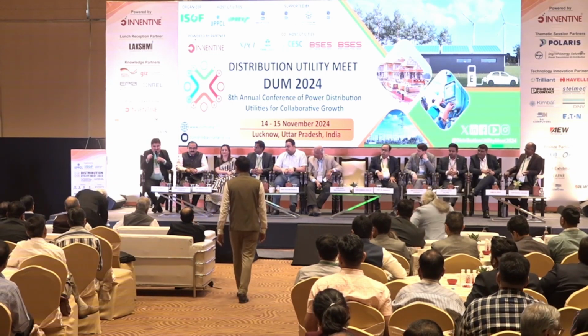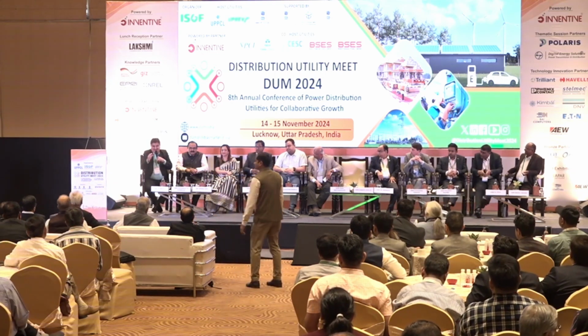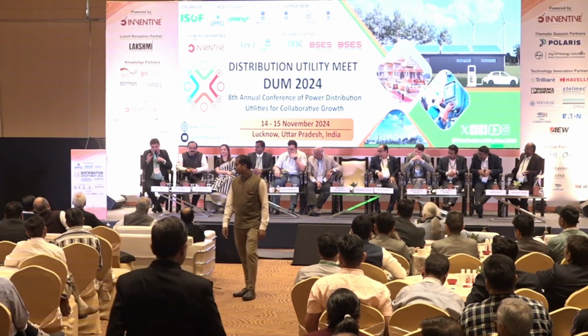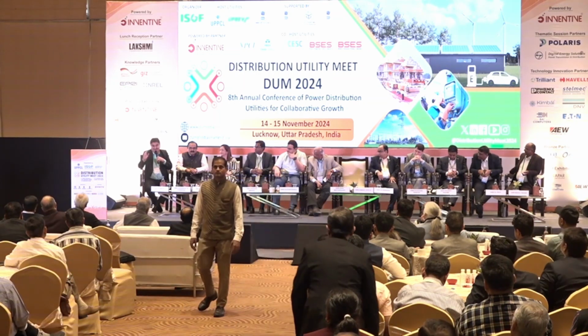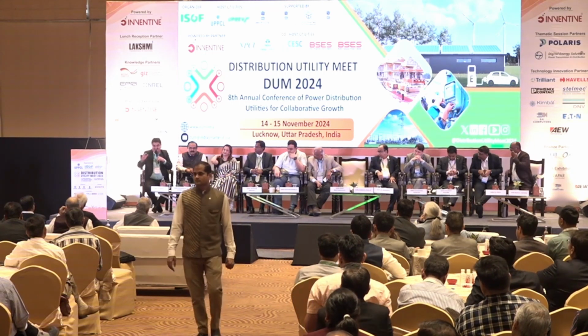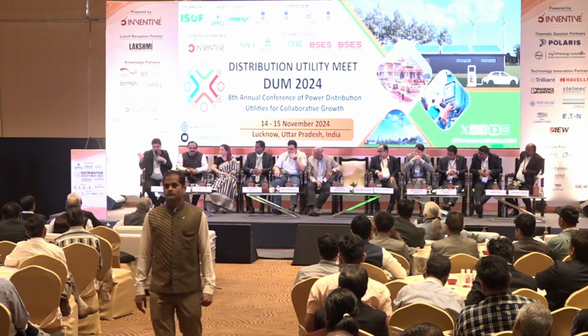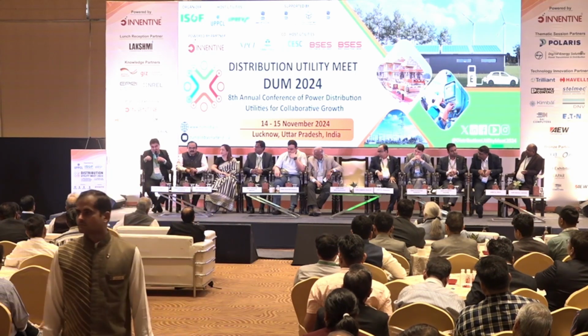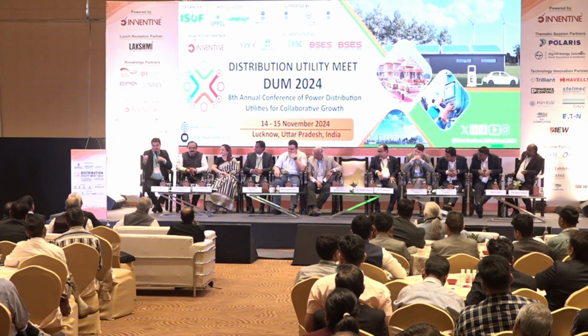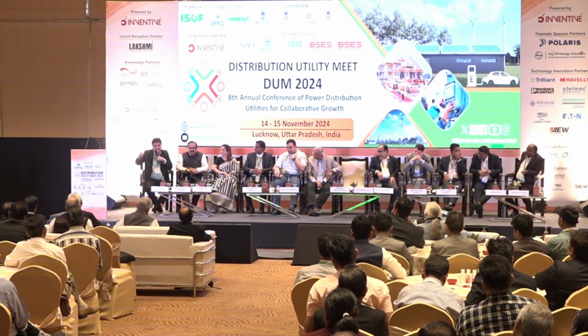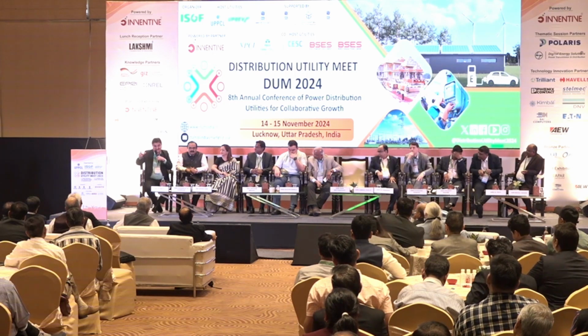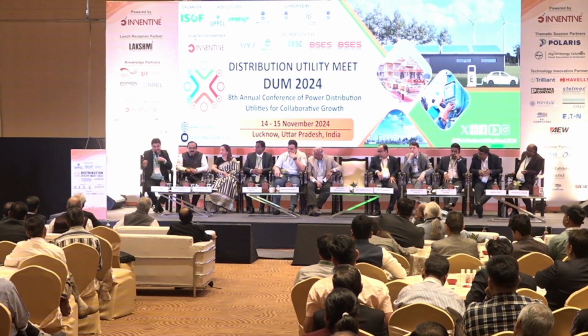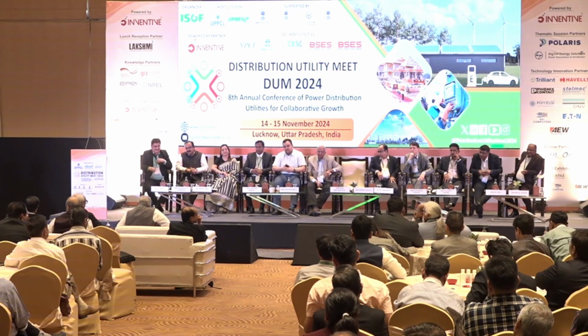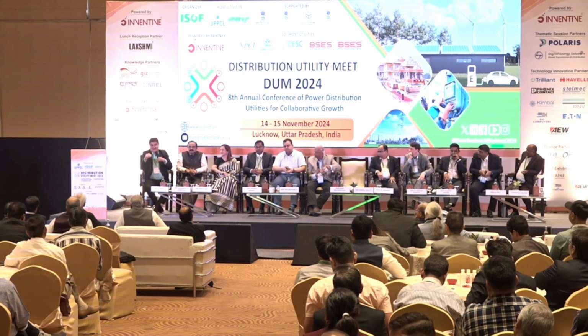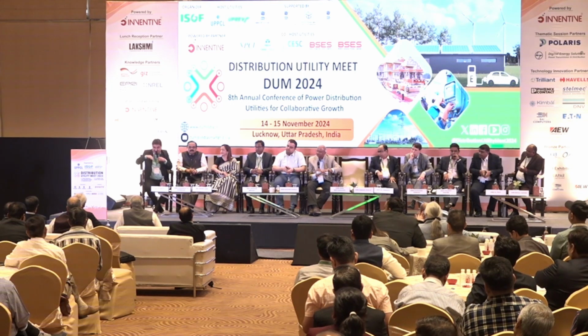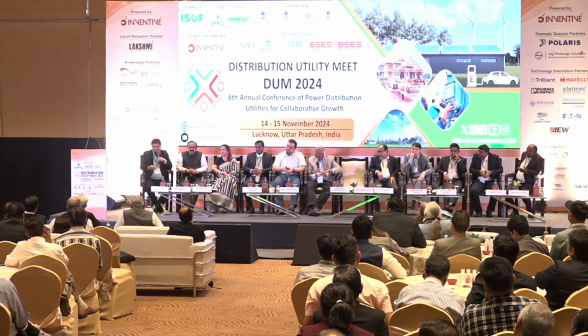I'll just repeat what I said: these are line frequency inverters. Even a 5 megawatt ground-mounted solar PV plant does not generate power if there's no grid. So it's safe—it never sends power to the grid if the grid is off. Even a 3 kilowatt domestic rooftop solar will never send power if the distribution transformer is taken out for maintenance, or a section of the line is taken out for maintenance. That's why these are not used for black start procedures. There's a disadvantage too, but we never anticipate them working in a black start.